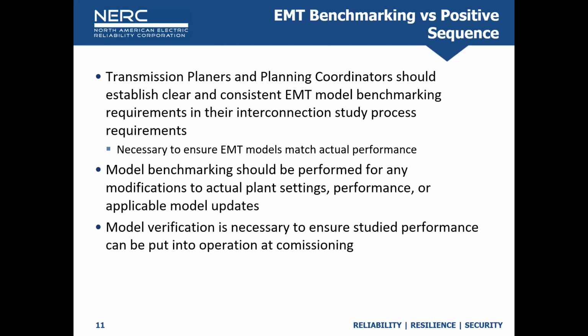Checks happen back and forth between the entities and generator owners or OEMs to make sure that anything applicable gets re-studied. Applicable in this case means something that changes the performance of the plant. For other things, like a new model version, the advice is to look at what that change actually affects—maybe it's a change for a model used in Germany but not in the US, so it's probably not applicable, and you don't need to re-benchmark for your US facility. Generally, model verification is necessary to ensure the studied performance can actually be put into commissioning.